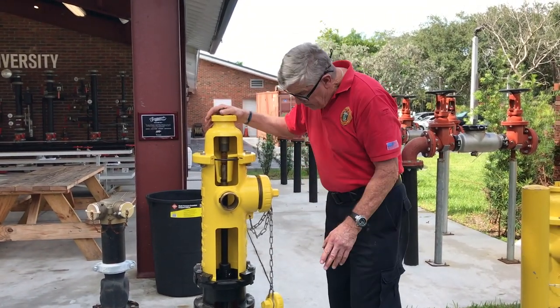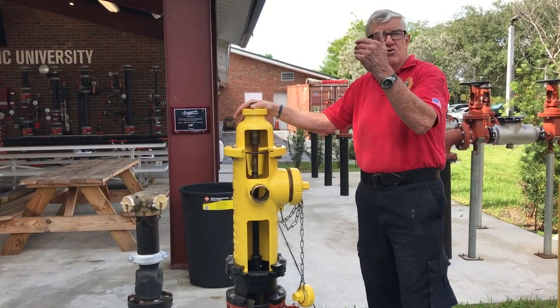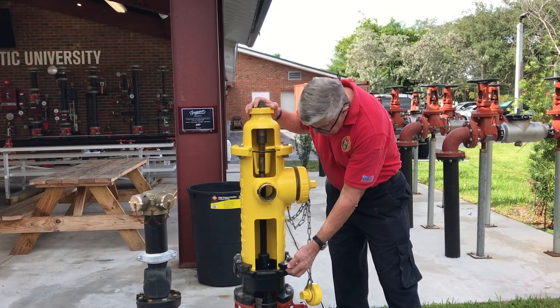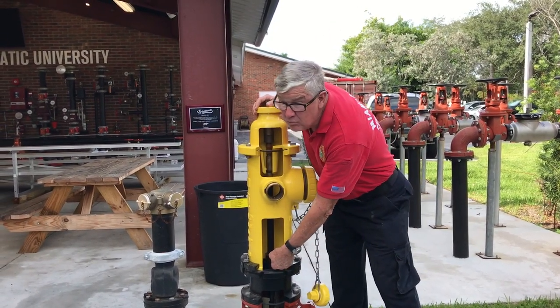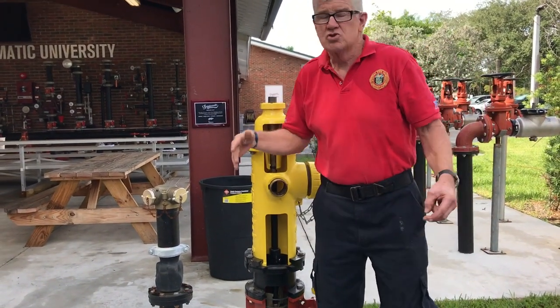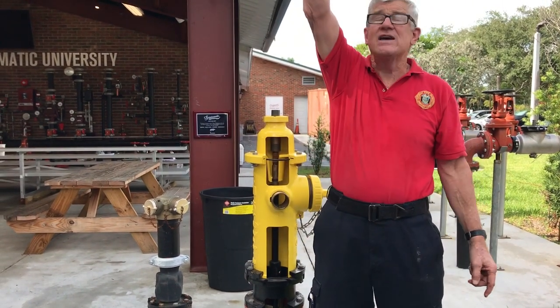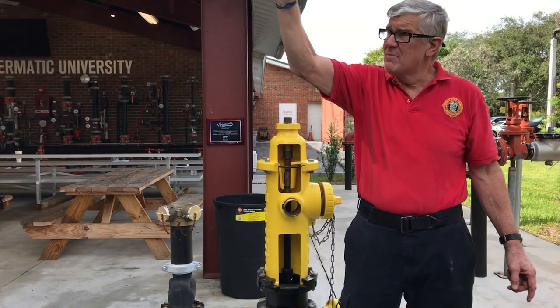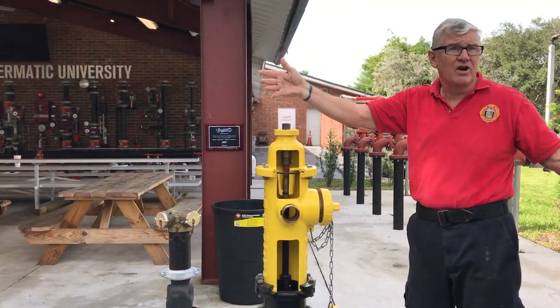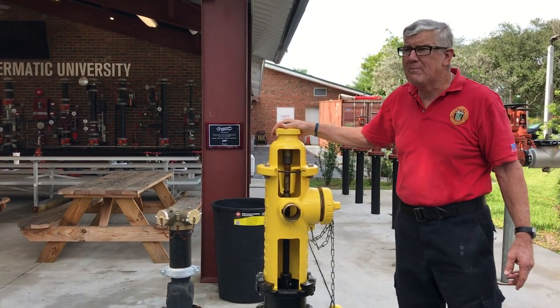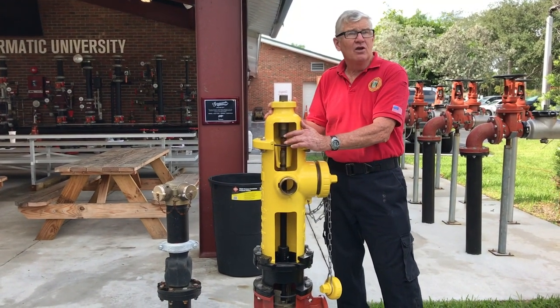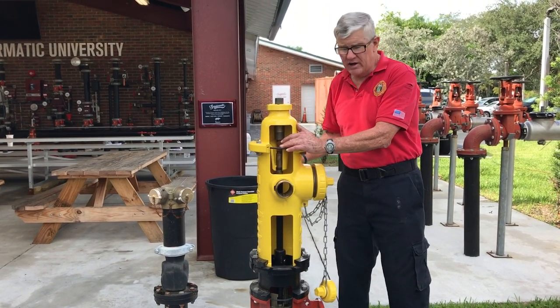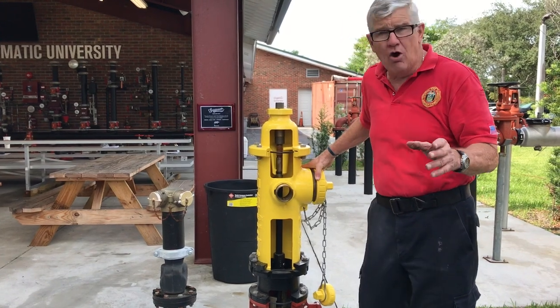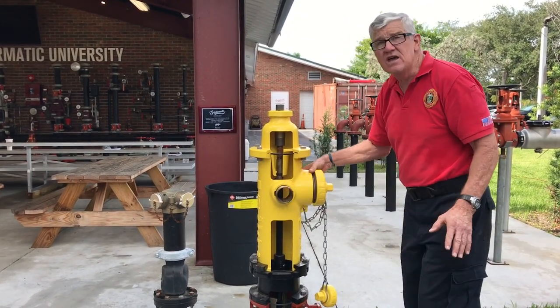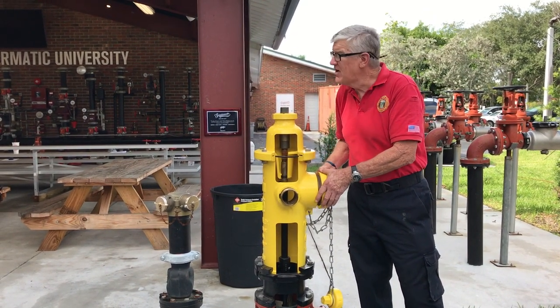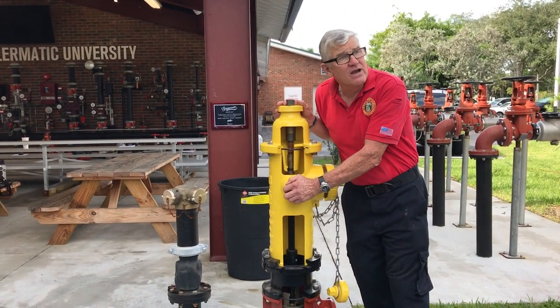So dry barrel hydrant. This one is equipped with what we call a traffic flange. So if you hit it in your car, it has a tendency to break at this frangible connection right here. Also, the stem will separate. Two reasons. One, so it doesn't kill you. Secondly, so we don't have a geyser shooting 30 feet up in the air. Now, there is another type of hydrant that you see primarily in the Los Angeles area, that part of the country. Because they don't have freezing weather there, they have what's called wet barrel hydrants, where all the way up to the top is water and you have an individual control for each outlet. Remember that a hydrant is designed to flow its rated capacity with all the openings flowing. So at the very least, what we want to do is put a gate valve on here.